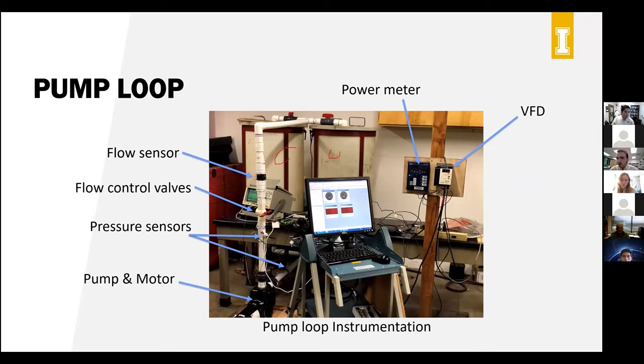The whole system is controlled through the VFD there on the right. It allows for precise control of what frequencies we want to run the motor at. There's a power meter from SEL that allows for the measure of power consumption over time. There are different sensors listed here, and a pump is on the bottom. So we monitor the pressure on both sides of the pump, the inlet and the outlet, so we get the pressure difference across the pump. There's a flow valve to restrict how much flow is going through the system, and then a flow sensor to monitor that flow.